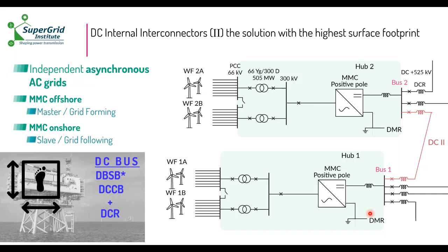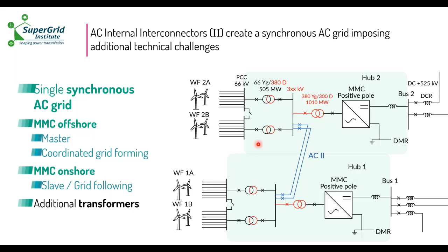In the case of the AC interconnector, it has less transmission capacity, so you need two lines there. The network is the AC collector network, a single synchronous AC grid. You need an additional transformer to suppress the DC offset that will appear between both MMCs. So this has to be taken into account in the economic study. I forgot to say in the last slide, but here as well, the MMCs on this part are controlled in grid forming control, so they support the voltage and frequency of this grid. In this one they act independently, but in this one they coordinate to control voltage and frequency.